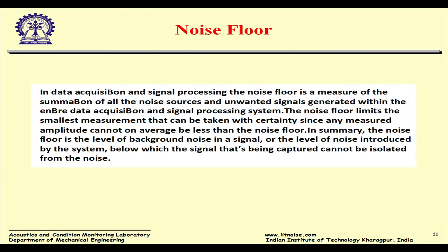And this noise floor is the lowest value which we can measure. There have been instances where even in our lab we have gone down to about 28, 26 decibels. But if your product is producing noise, say at 25 decibels, we need to have a noise floor much beyond that, at least 10 dB less than the level which you are measuring.